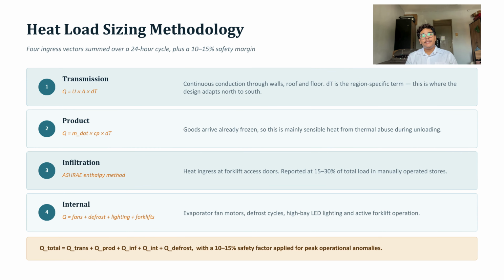So, before selecting a compressor, we must determine the total heat load, which comes from our four ingress factors summed over a 24-hour life cycle. First is transmission, representing heat continuously conducting through the wall, roof, and floor. It depends on the region's temperature differential, which is how our design scales across Peninsular Malaysia. Second is the product load, which consists mainly of sensible heat from thermal abuse when frozen goods are unloaded. Thirdly, the infiltration. This infiltration comes from the forklift access door. It is quantified using the ASHRAE enthalpy method and reported at 15 to 30% of the total load, making it a critical factor.